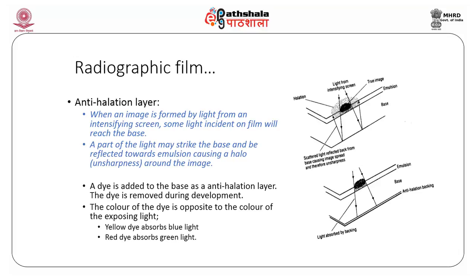There is also an anti-halation layer. When an image is formed by light from an intensifying screen, some light incident on the film will reach the base. A part of this light may strike the base and be reflected back towards the emulsion, causing a halo effect as seen in this figure — a black dot surrounded by many minute dots. To get rid of this halation effect, a dye is added to the base as an anti-halation layer; the dye is removed during processing. The color of the dye is opposite to the color of the exposed light — for example, yellow dye absorbs blue light, and red dye absorbs green light.